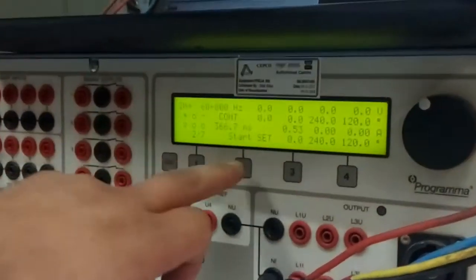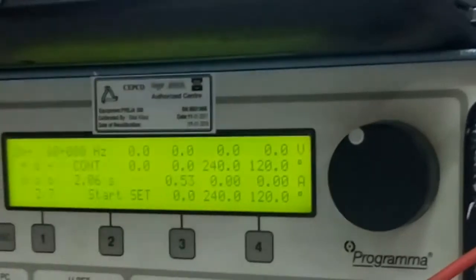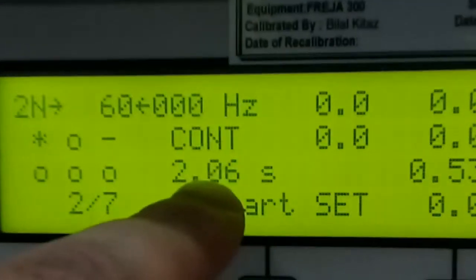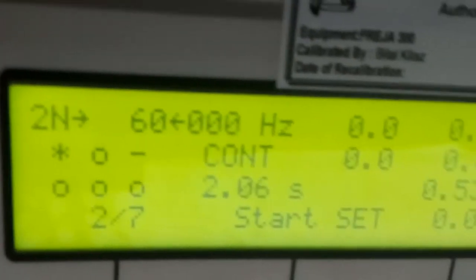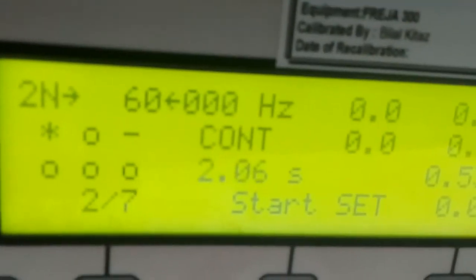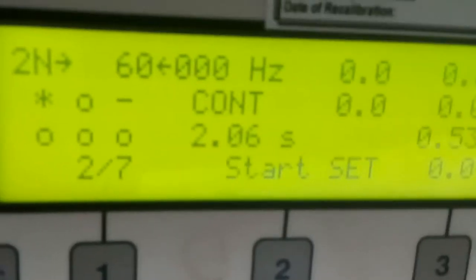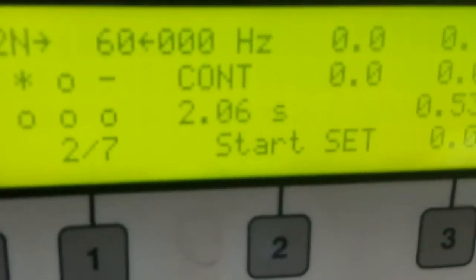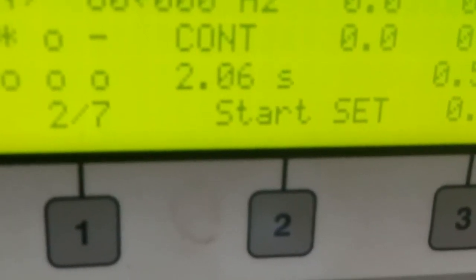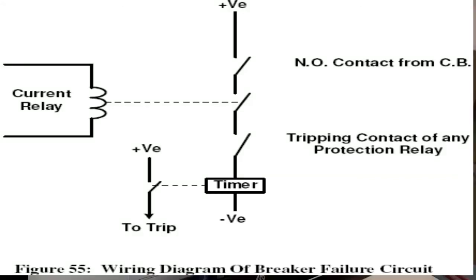Now connecting the breaker failure activation output and injecting again. After 2.06 seconds, the contact picks — the breaker failure activation contact closed after 2.06 seconds. The breaker failure delay was set to 2 seconds, confirming the relay operates correctly. After this time, it initiates the command to trip the incomer, bus section, or anything related to the fault, tripping all those circuit breakers. This concludes the whole concept of circuit breaker failure.